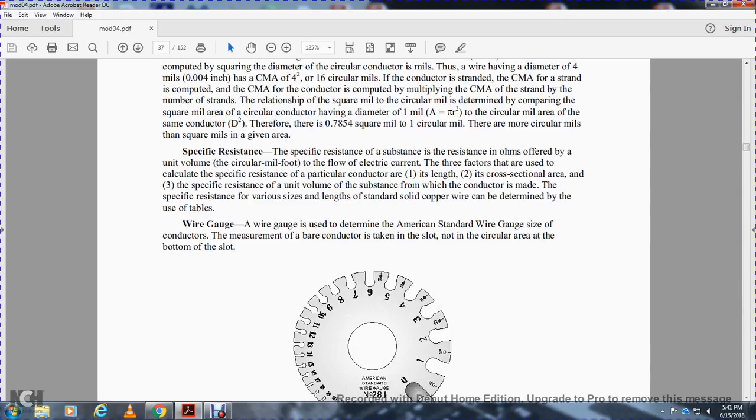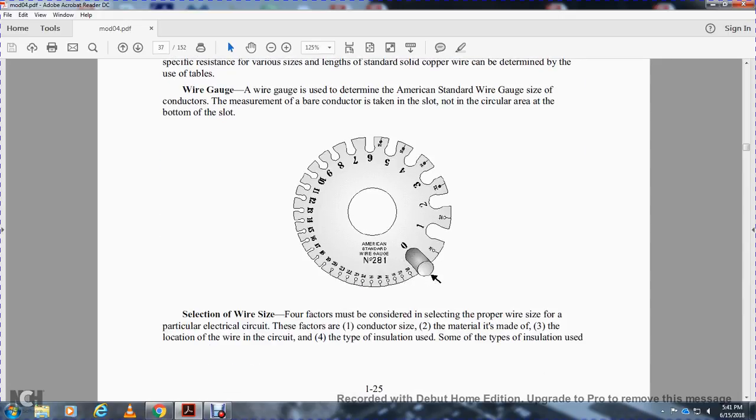A wire gauge is used to determine the American Standard Wire Gauge size. Measurements of bare conductors are taken in the slot, not in the circular area at the bottom of the slot. When selecting wire size, four factors must be considered: the conductor size, the materials it's made of, the location of the wire in the circuit, and the type of insulation used.